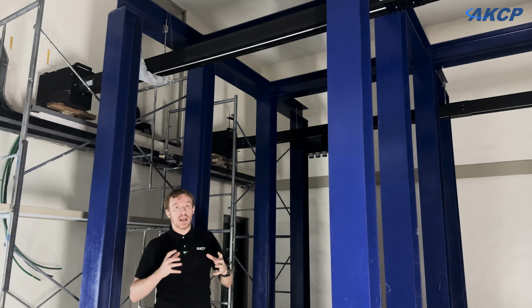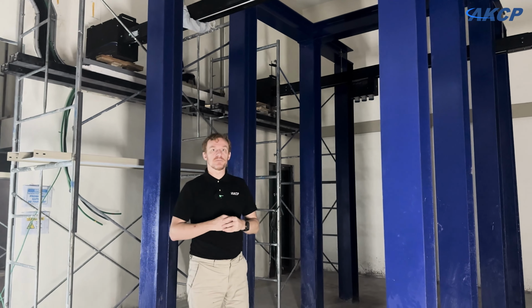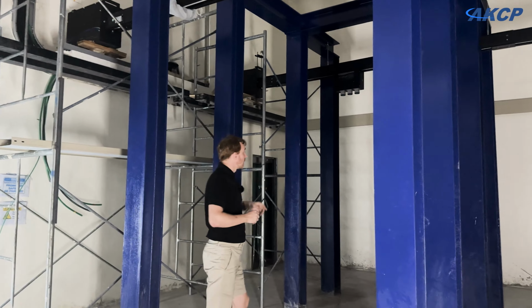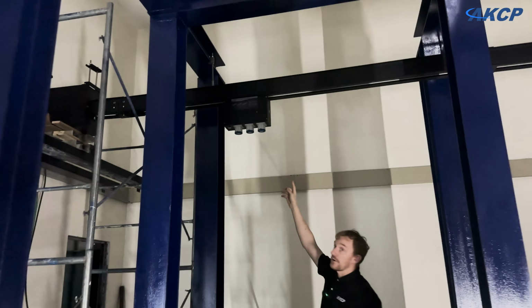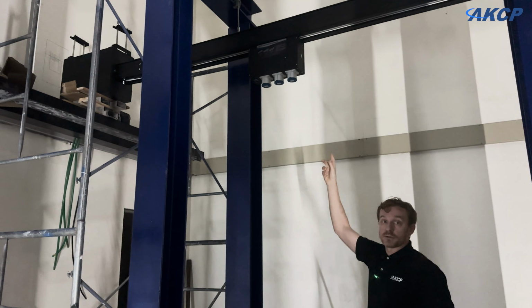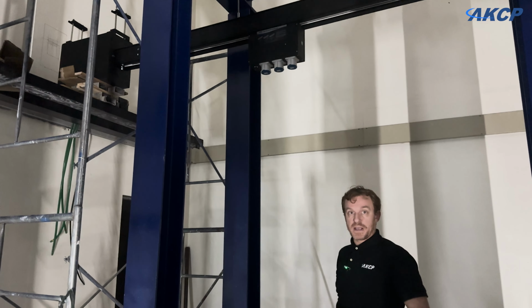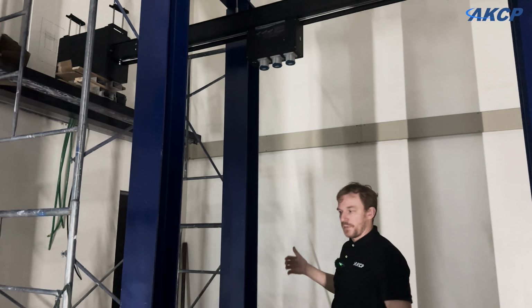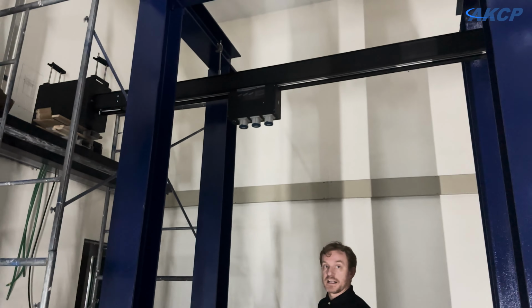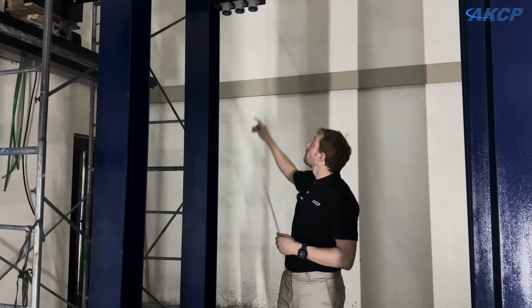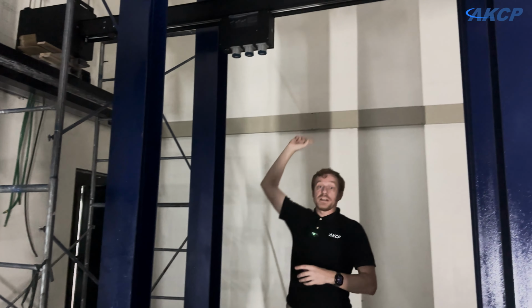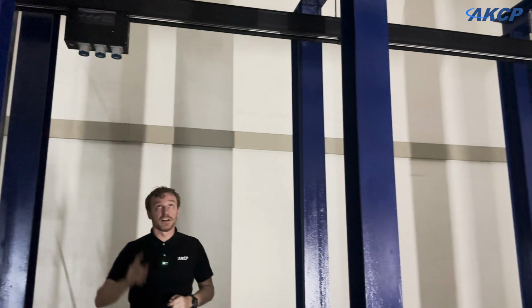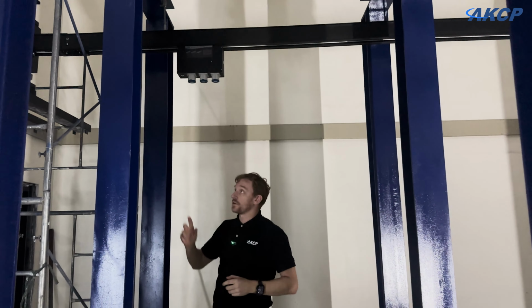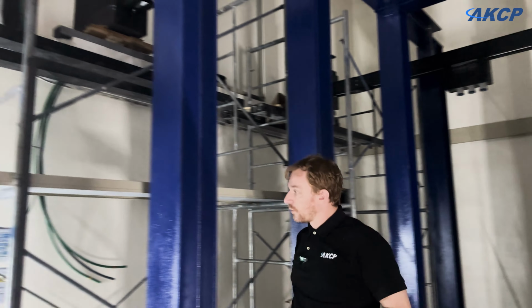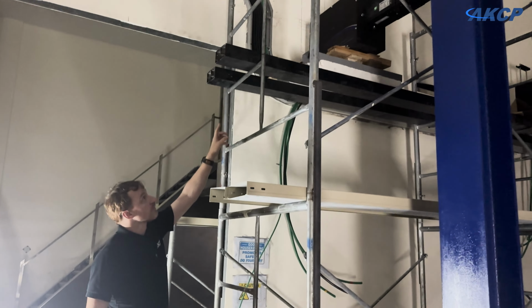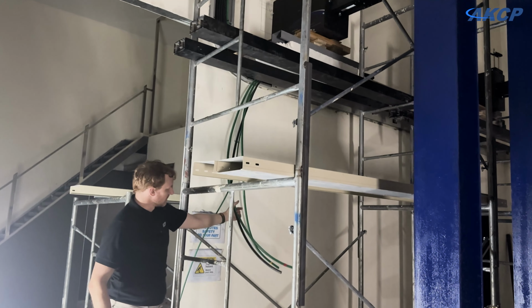On these bus ducts we have distribution boxes, or breakout boxes - you can see we've got one already installed over there. This breakout box has 3 power connectors on the bottom, and into that we'll be able to plug in our space heaters, which we're using to simulate 9 kilowatts of power per rack. We have 3 sets of space heaters, 3 kilowatts, 3 kilowatts, 3 kilowatts, hence the 3 sockets. This will be repeated all the way along here. We have 6 of those breakout boxes, another 6 on the other side, and that's our power distribution. That comes back to a main box at the wall here, which is currently being installed, and that will have these wires terminated to it.